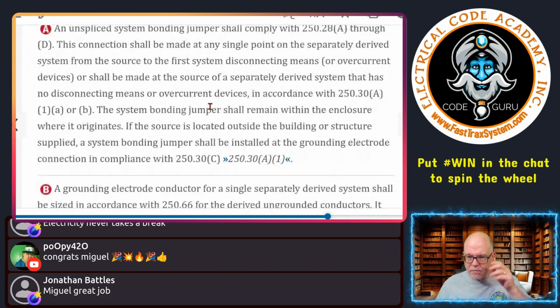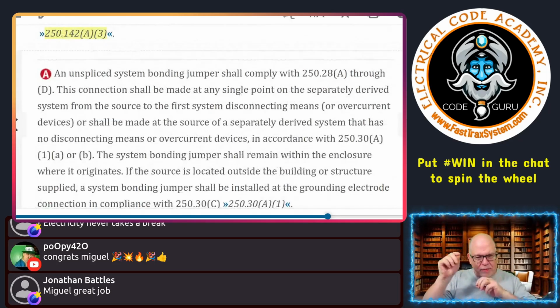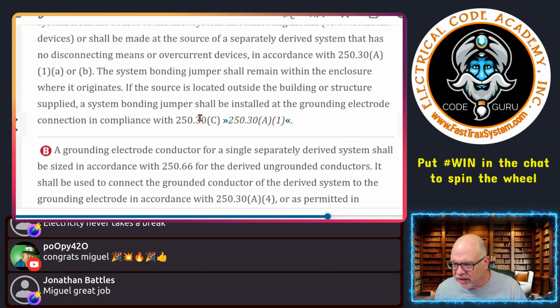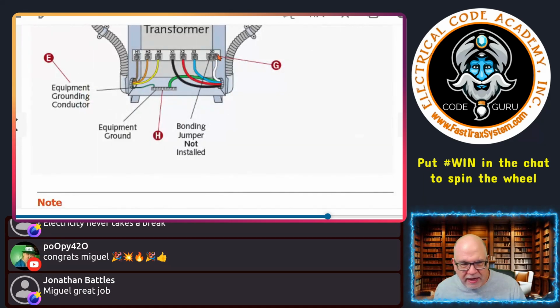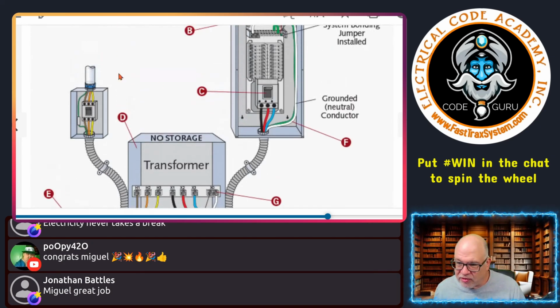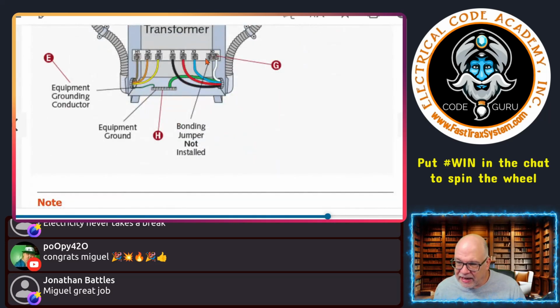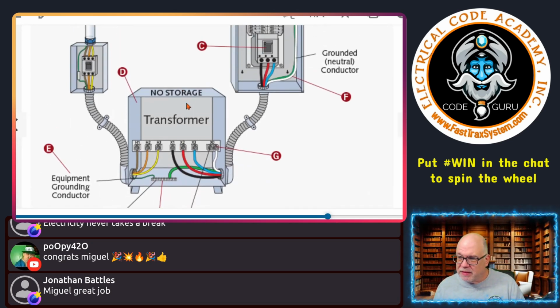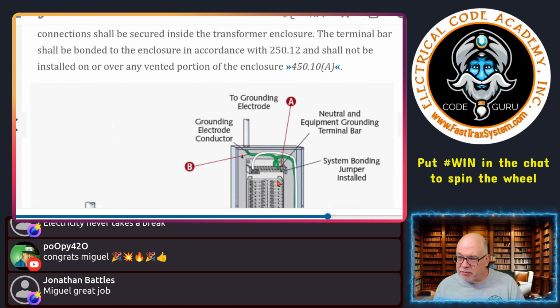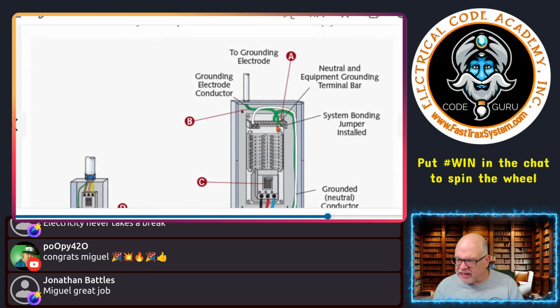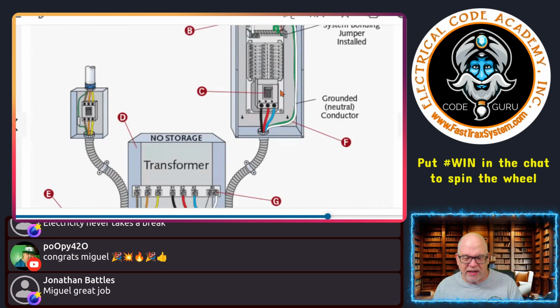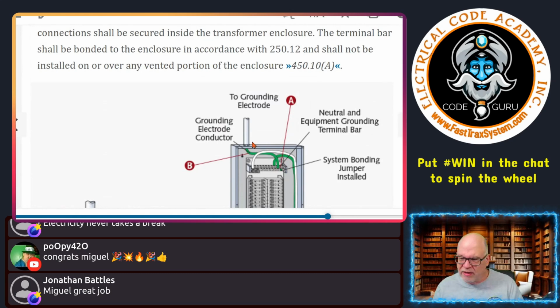Okay, now, as far as that system bonding jumper, that connection, I'll show you in an example here real quick, right here, from here XO, down to here. I could have the system bonding jumper right here. And that's going to connect, again, this is in a transformer. That could connect the XO to the frame or to the case. That is that allowance in 250.30. But I also have an option to do it here at the first disconnecting means location, right here on the secondary side. So I have an option to do it here or do it here.